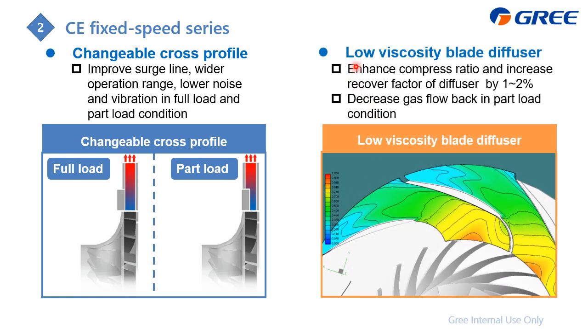And the next is the low viscosity blade diffuser. For this one, we just ensure the inside structure of the impeller is more smooth for the refrigerant flow. This can decrease the resistance and also lower the potential of the surge.